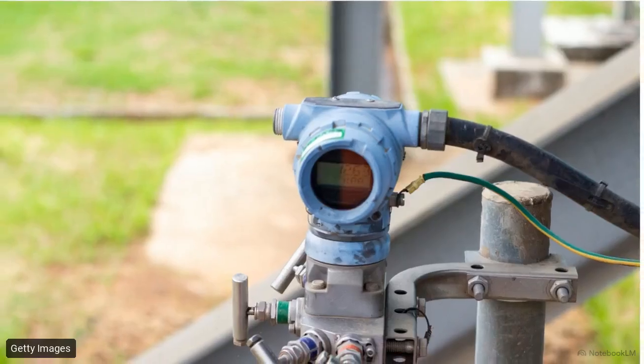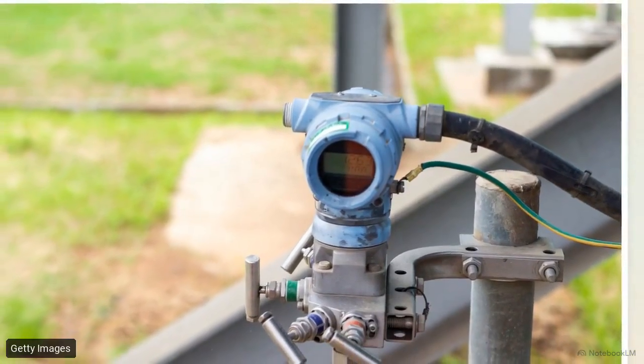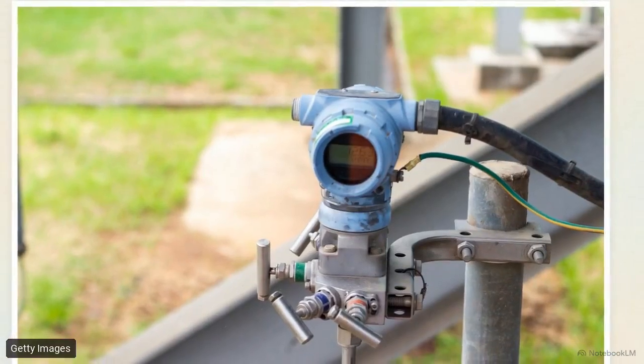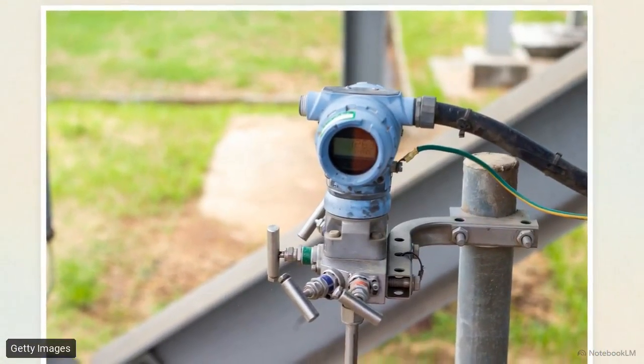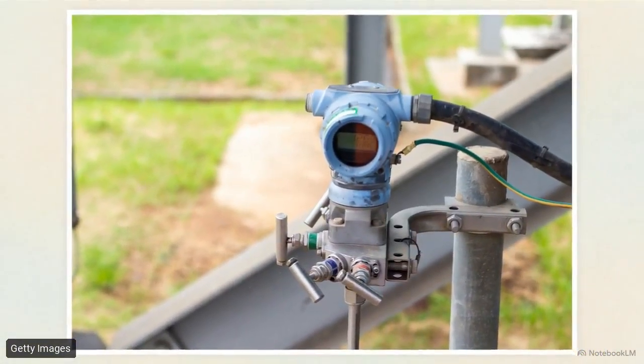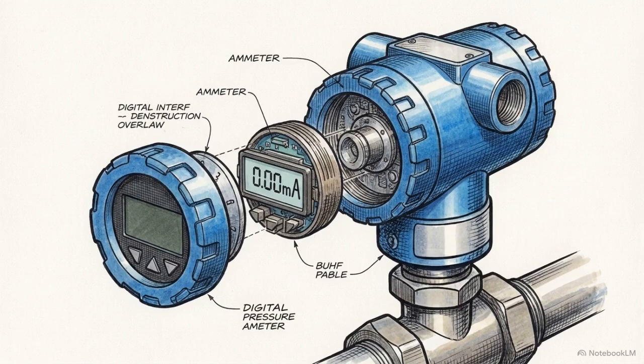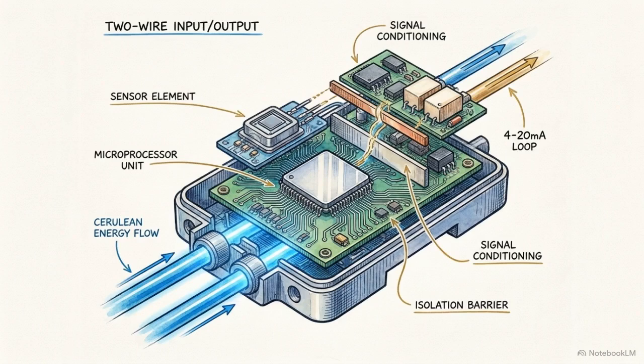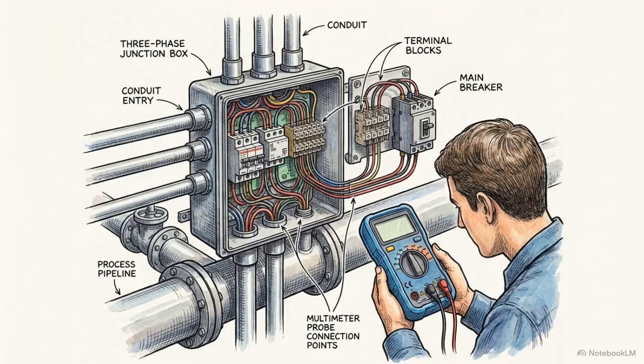Modern transmitters are incredibly efficient, designed to operate on as little as 3.5 milliamps, leaving a safe buffer above the fault detection threshold. If the loop dropped to zero for a zero reading, the field device would instantly shut down. The 4 milliamp offset is a strictly necessary mechanism for delivering power. This continuous, closed-loop system creates a paradox when technicians need to verify calibration in the field.